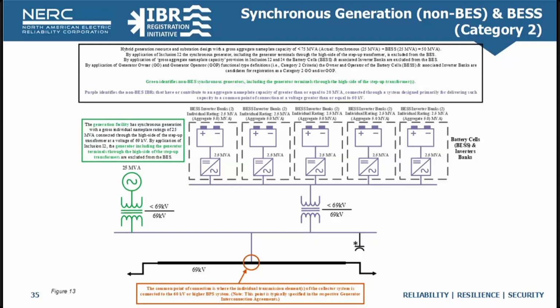First step in this scenario, again, is to apply the BES definition to the facilities. So by application of the definition, with a connection voltage of 69 kV, the 25 MVA synchronous generator and the 25 MVA battery energy storage component are excluded from the bulk electric system. The second step in evaluating this example is to apply the Category 2 criteria to the battery energy storage system facilities. So by application of the Category 2 criteria, aggregate nameplate rating provision of greater than or equal to 20 MVA with a connection voltage of 69 kV, the 25 MVA battery energy storage component exceeds the 20 MVA threshold, and therefore the owner and operator of the battery energy storage component are candidates for registration as a Category 2 GO and Category 2 GOP.